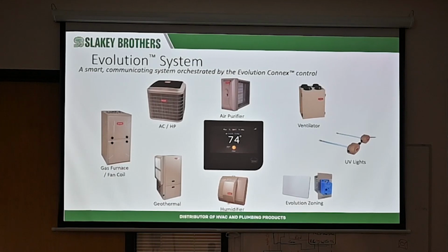Humidifier pad. It's a timer that, when you engage it, yes, it is going to activate the timer, but it does also activate the humidifier terminal for the furnace or the geothermal or the fan coil, because those circuit boards have a humidifier terminal. And so if you have a humidifier with the Connex, you don't have to put in a separate humidistat. We'll discuss that a little bit later, but it's just a little family of the equipment.